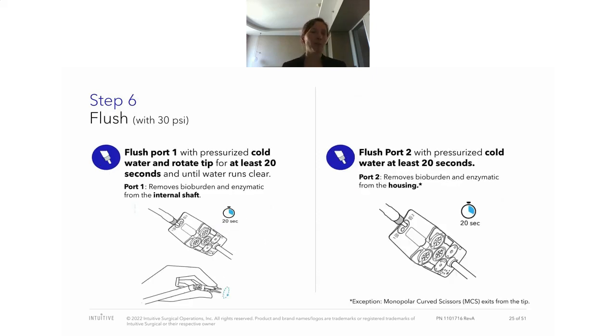After that, we go to the flushing step. And now both flush ports are flushed. Flush port 1 with cold water. And very important here is also that while you flush, the tip is rotated to make sure that all the cables move through the tip, and also the seal that reduces the amount of blood that can go into the instrument, so that everything is cleaned out of there.